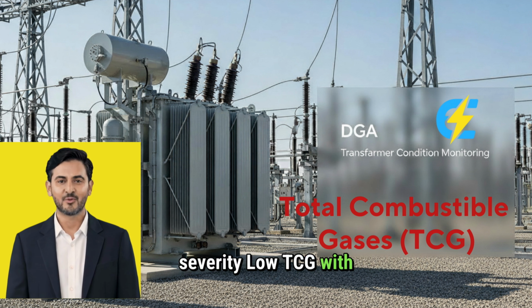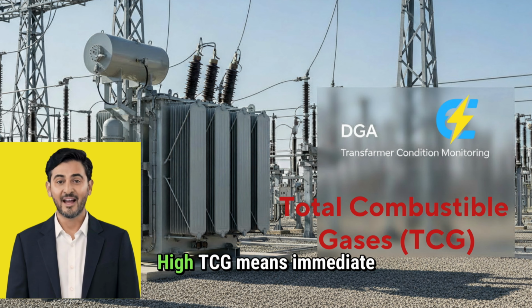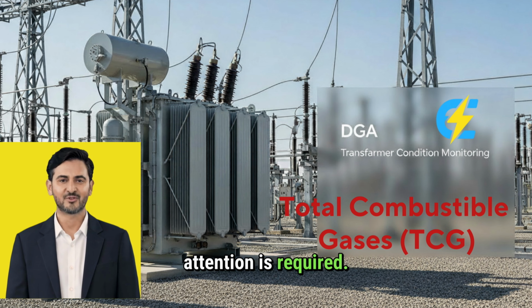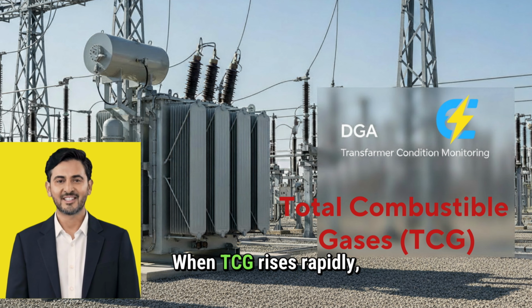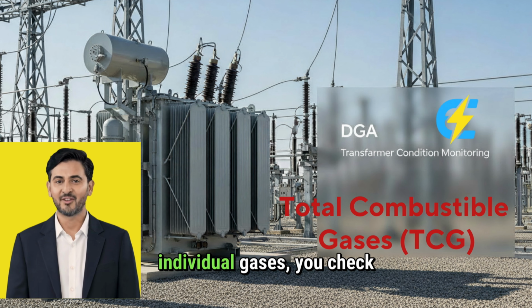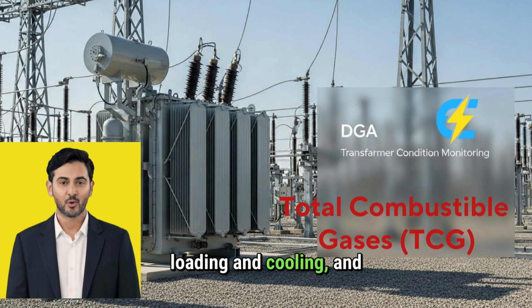Low TCG with stable trend means normal operation. Rising TCG means fault energy is increasing. High TCG means immediate attention is required. When TCG rises rapidly, you don't debate limits. You correlate with individual gases, you check loading and cooling, and you plan corrective action.